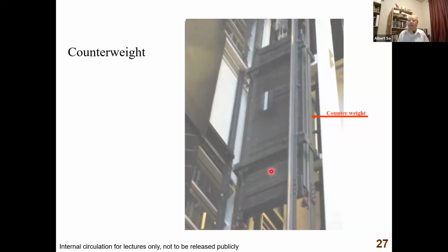They are strips. They are metal or concrete strips on the counterweight, because they put the counterweight on one by one. Okay, suppose each strip is 5% of the total weight, then you need 20 strips. The counterweight is used to balance, okay, the force from the car.